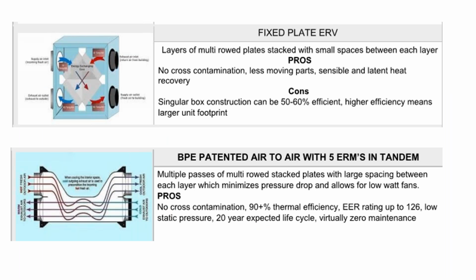There are a couple of different styles. We have the single box, and then we have the multi-box units. The multiple stacked plates have small spaces between each layer, so there won't be any cross-contamination. There are very few moving parts, and sensible and latent heat are recovered. The bad thing is you're only getting about 50% efficiency. I know they say 50 to 60, but realistically you're getting 50%. And to get more efficiency, you just have to keep increasing the footprint or units.